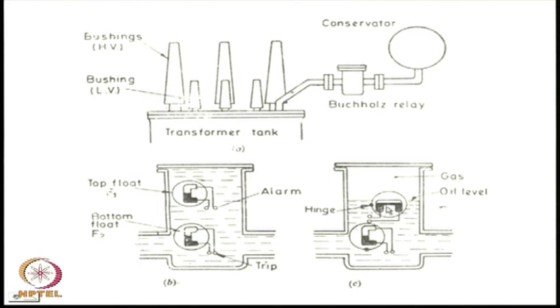However, a normal overcurrent or overcurrent for a small duration will not produce enough gas to make the bottom float operate. This will happen only if there is a severe or a direct short circuit and violent gas generation, then the level will go down further and even the contact of the bottom float will be closed. This float is connected to a trip circuit which will close the tripping circuit of a circuit breaker and the transformer will be disconnected. So, this Buchholz relay is used with many large size 3-phase transformers.